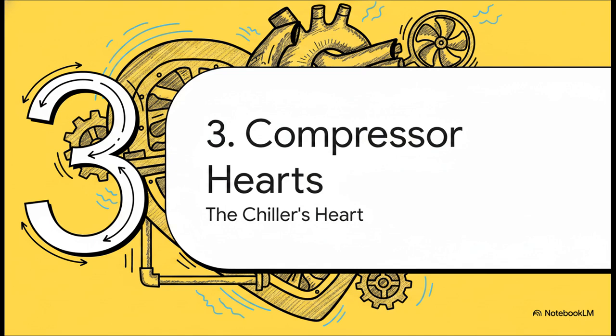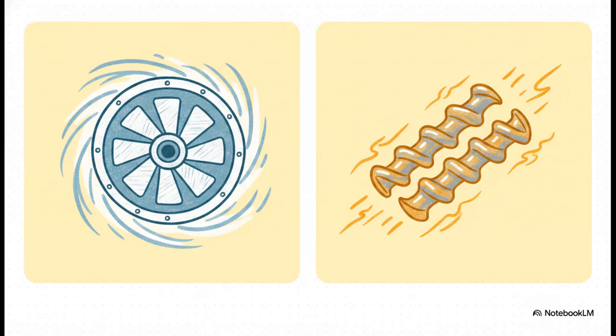Okay, Section 3, compressors, the chiller's heart. Now that we understand how the heat is displaced into either water or air, let's look deeper at the mechanical heart of the chiller, the part that actually compresses the refrigerant and pumps the system. Engineers generally choose between two types. First, the centrifugal, or turbo compressor. This absolute beast uses a spinning impeller to handle huge capacities. We're talking 500 to over 3,000 refrigeration tons in a single unit. That makes it the standard for hyperscale water-cooled operations.